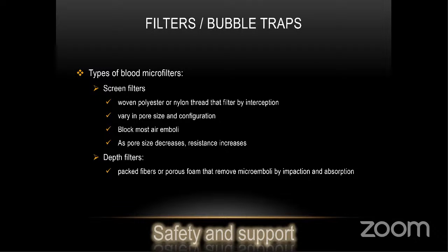As pore size decreases, the resistance through the filter increases, and it blocks most air emboli. A depth filter is a packed filter or porous foam that removes microemboli by impaction and absorption.